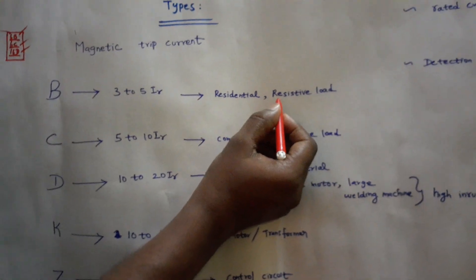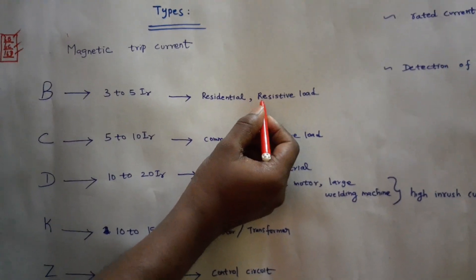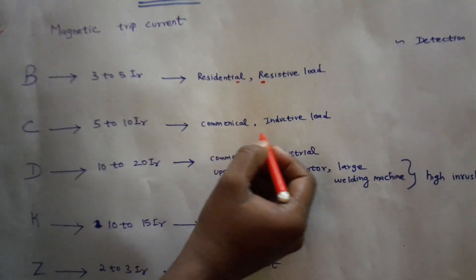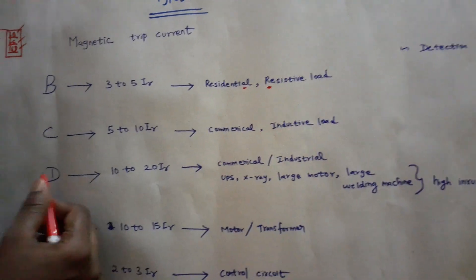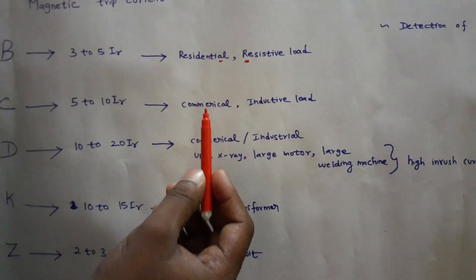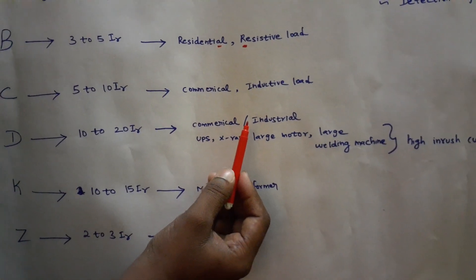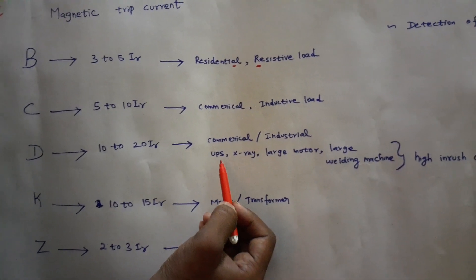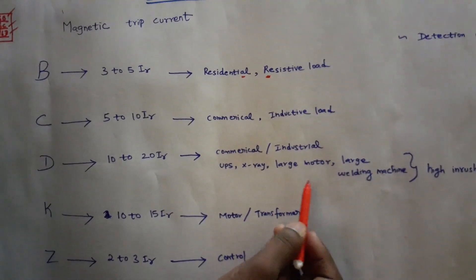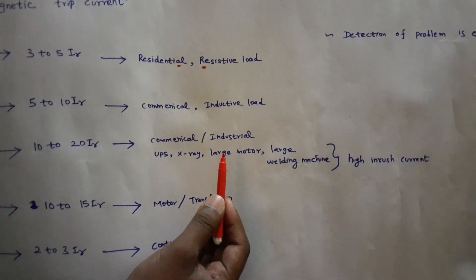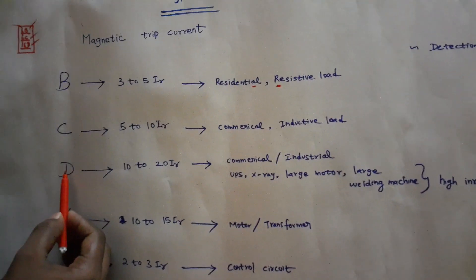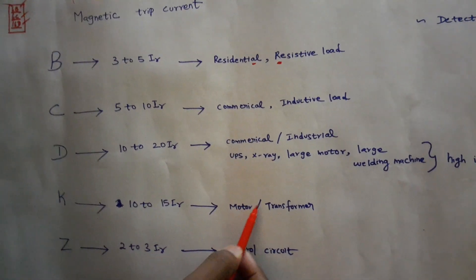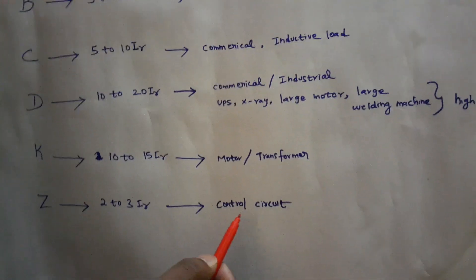B type breaker is used for resistive loads and residential applications. C type is used for commercial and inductive load applications. D type is used for commercial and industrial applications with high inrush current, such as UPS, X-ray machines, large motors, and large welding machines. K type is used for motor and transformer protection. Z type is used for control circuits.